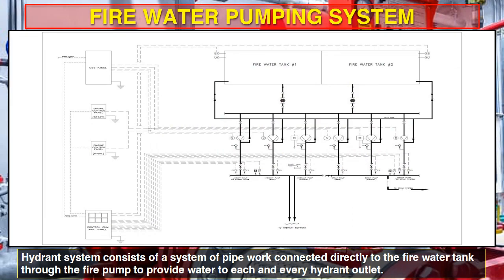We are now entering the core topic. The fire water pump house is the heart of the fire protection system because it pumps water to the pipe network so as to extinguish fire. From the drawing of the fire water pump house, you can clearly see there are two tanks, two main pumps, two diesel pumps, and two jockey pumps connected to the suction header. There is a common recirculation line connected to the top of the water storage tank, and a common discharge header distributed to the spray headers, hydrant lines, etc. There are also various panels like MCC panel, engine control panel, and control cum annunciation panel to control the operation of pumps.